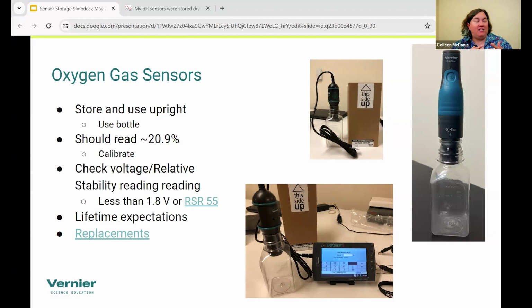The way we can tell is, if it's a LabQuest sensor, looking at the live voltage reading, or if it's a Go Direct sensor, looking at the RSR, relative stability units. Basically, if the value is below 1.8 volts or below 55 RSRs, that's a sign that the cell needs replacing. Similar to the pH, I say the cells will last anywhere from 6 to 8 years, depending again on how well they're stored and how they're used. Storing them upright is definitely key and critical. And not only do you need to store them upright, when you use them, you want to make sure they're being used upright as well. And like I said, once that cell ages out, we can do a refurbishment on them so you don't have to buy a whole new sensor. Again, saving costs.